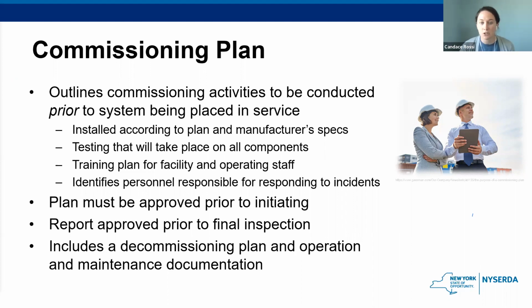They need to provide the verification that the required equipment and systems are installed in accordance with the approved plans. They'll need to do integrated testing for all fire and safety systems. They need to do testing for all required thermal management, ventilation, or exhaust systems associated with the energy storage system. They'll need to prepare and deliver operation and maintenance documentation, which we'll discuss more on the next slide. They'll need to provide training of the facility operating and maintenance staff, which will be important for your town. They need identification and documentation of the requirements for maintaining system performance to meet the original design intent during the operation phase.